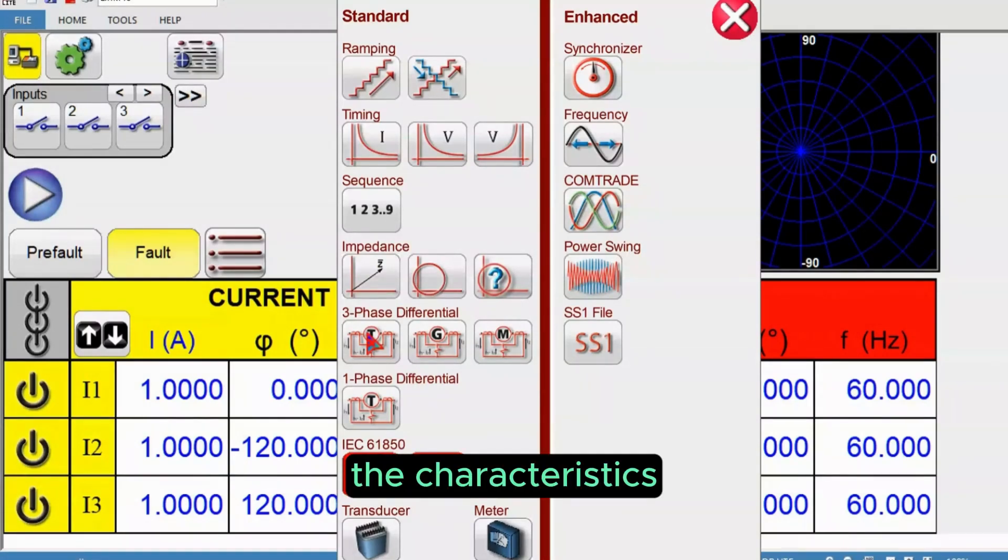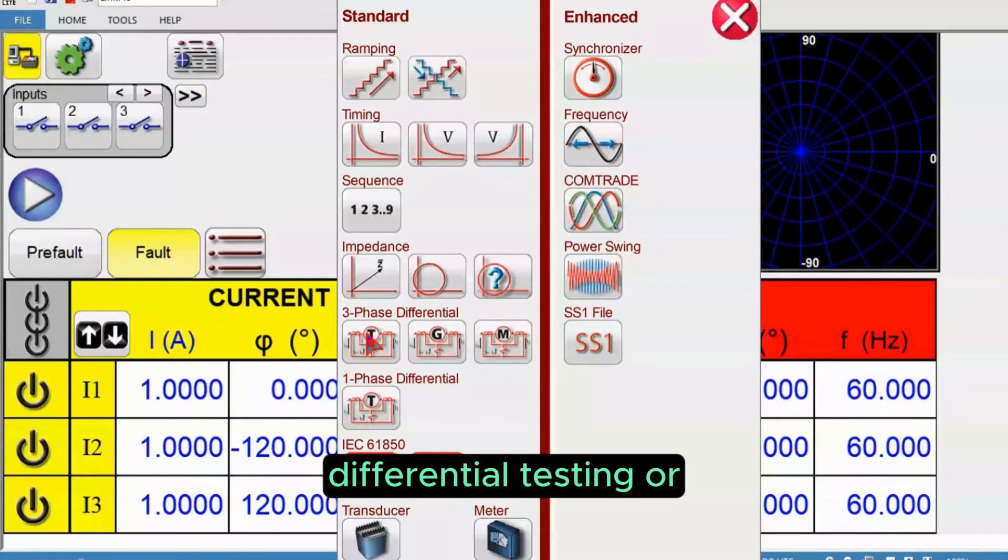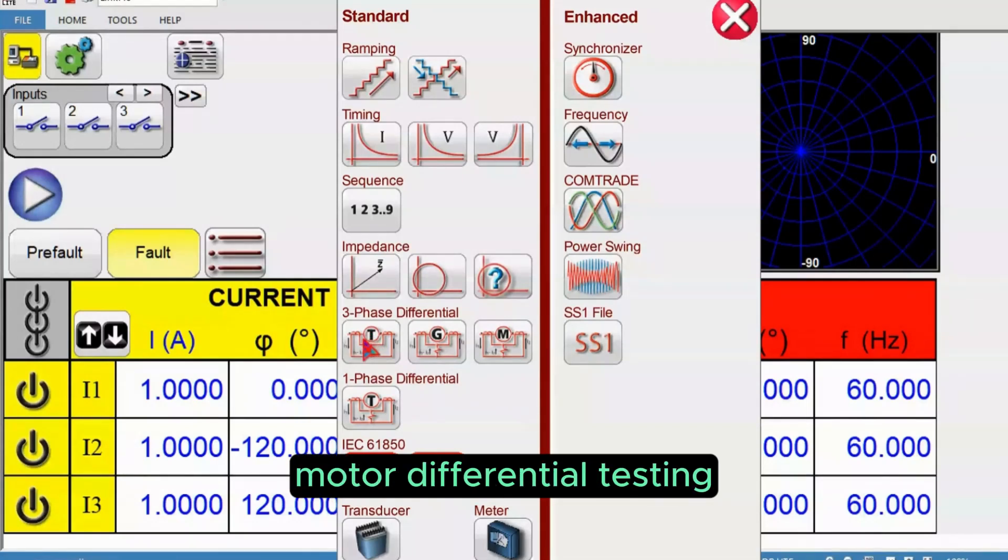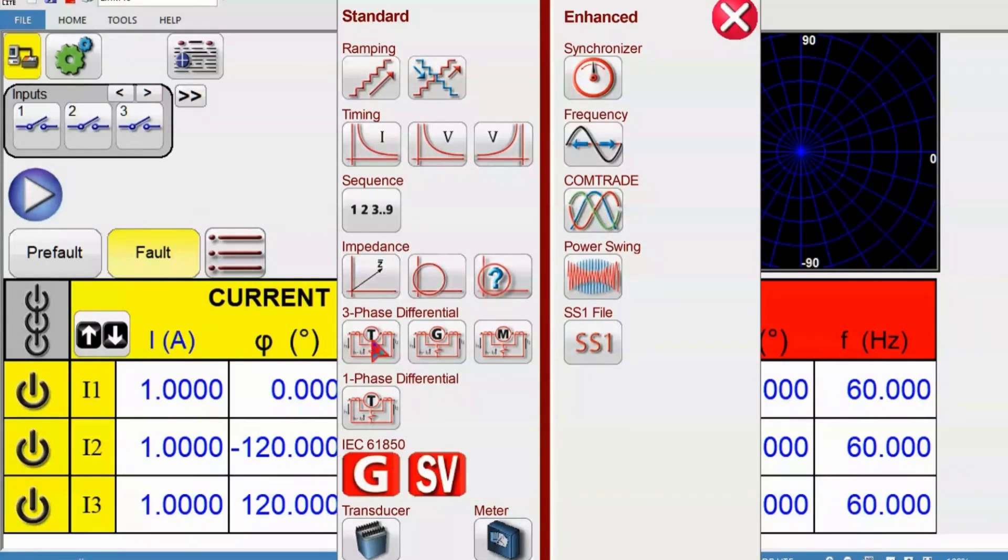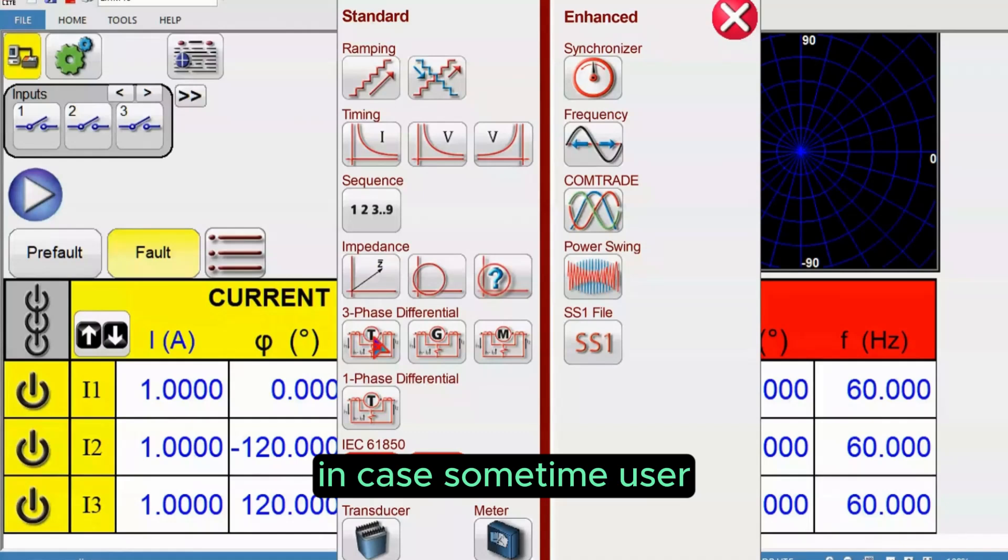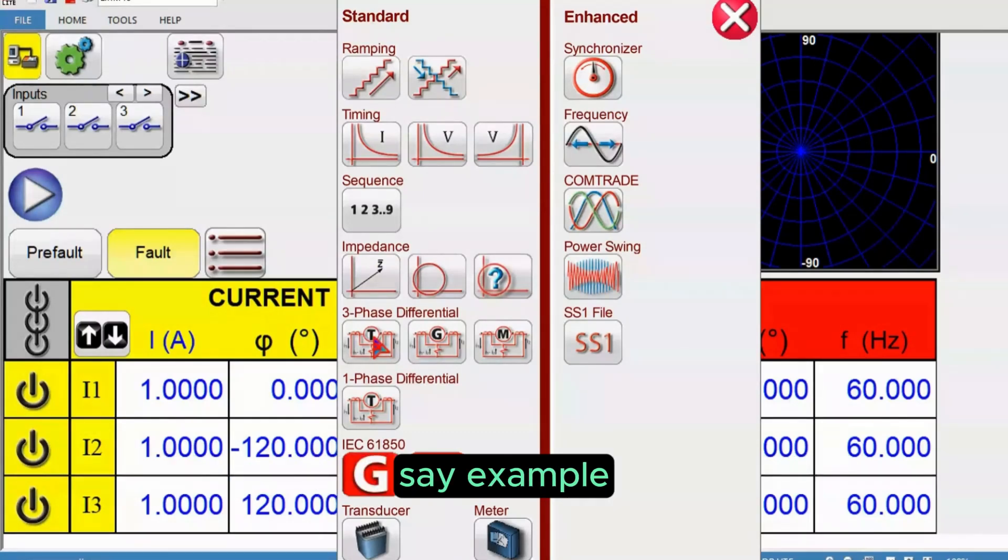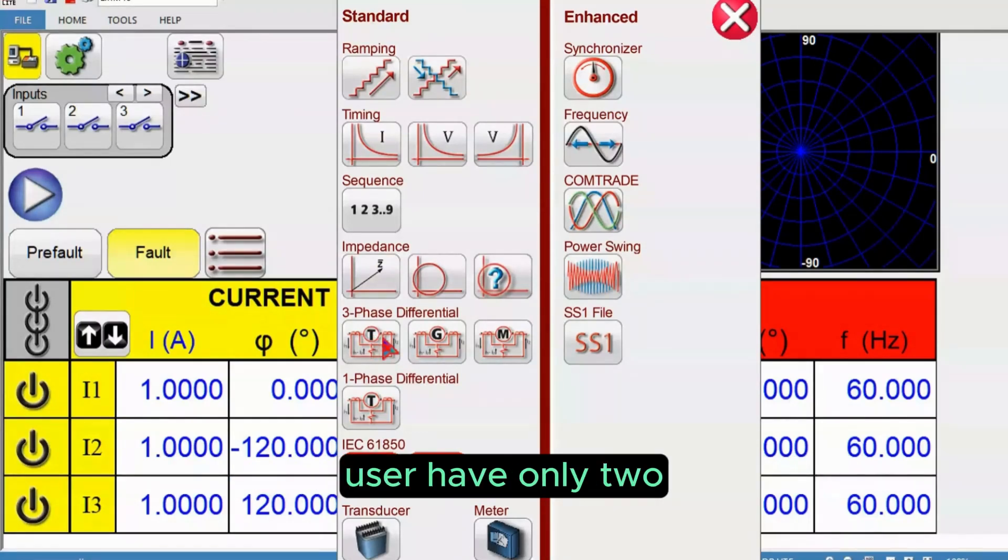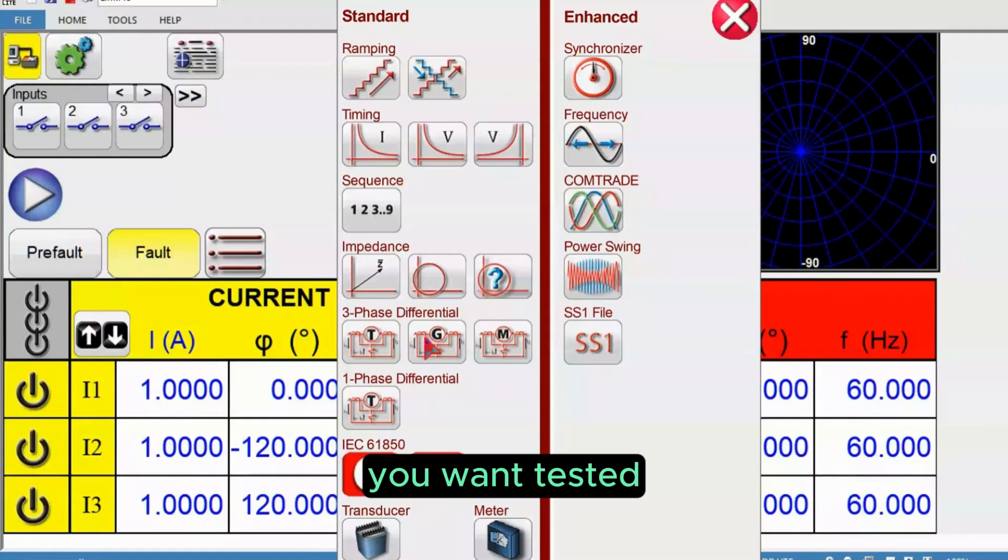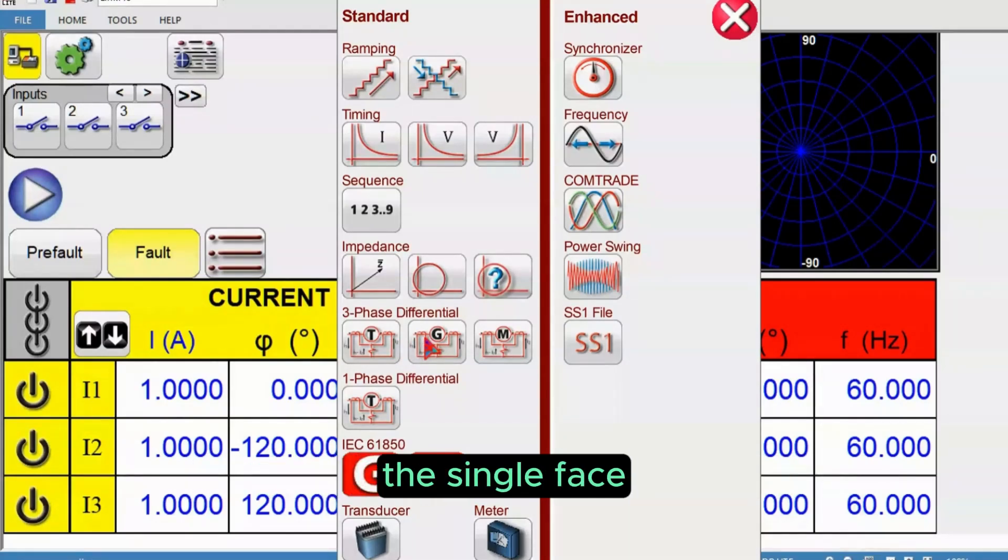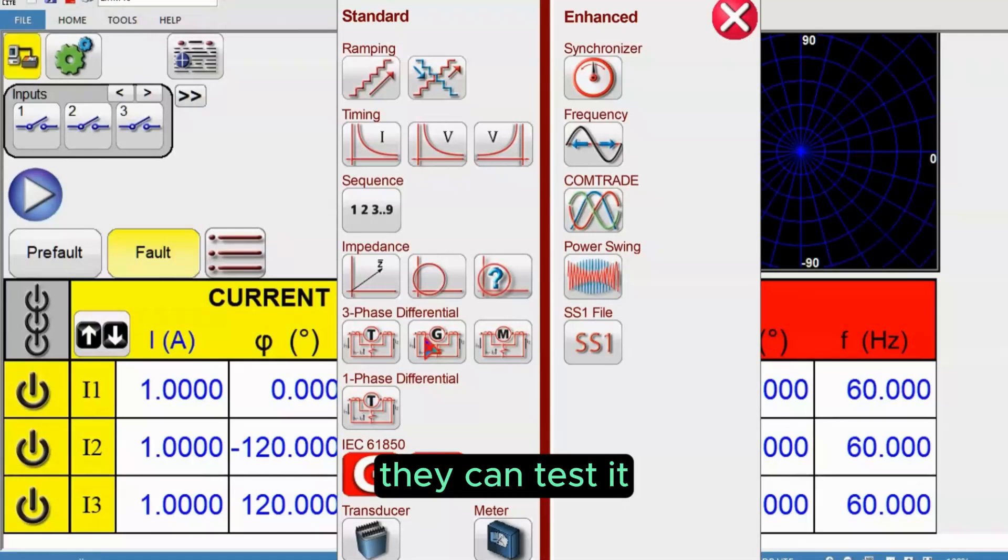It's the same for generator differential testing or motor differential testing. The tool is also available for single phase differential. For example, if users have only two current channel instruments like SMRT and want to test, then they can use the single phase differential module and test phase by phase.